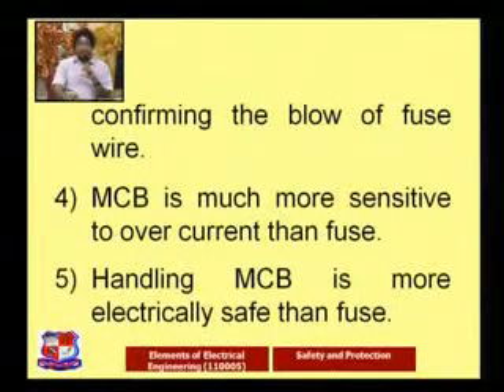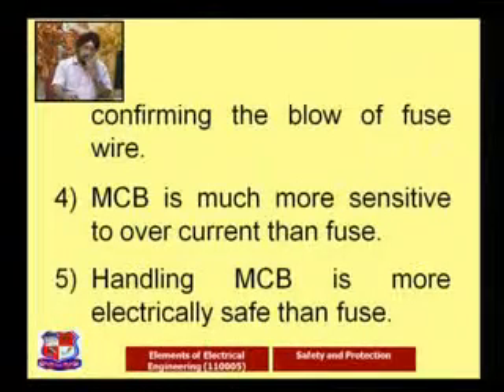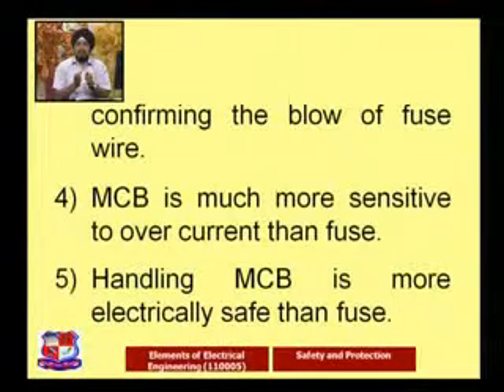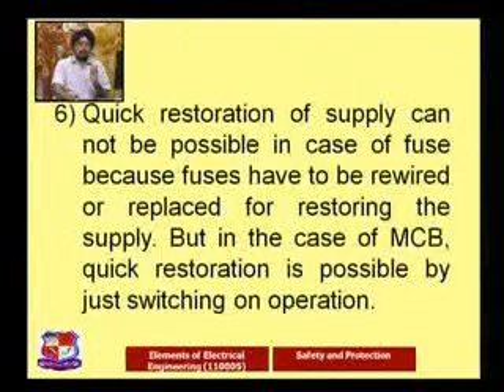MCB is much more sensitive to overcurrent than the fuse. The MCB can sense the fault very quickly and easily, and gives better protection compared to the fuse. And as it comes in a case, handling of the MCB is much safer compared to the fuse. Higher versions are going to come, and that's why the safety purpose is greater, as we are all doing this for equipment and human safety. So handling of the MCB is much more electrically safe compared to the fuse.